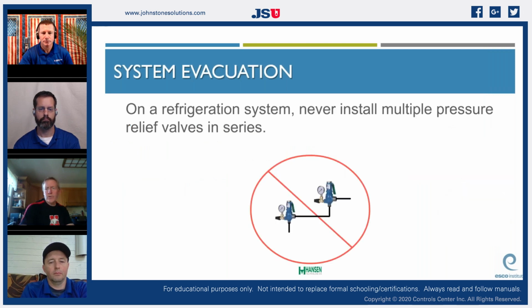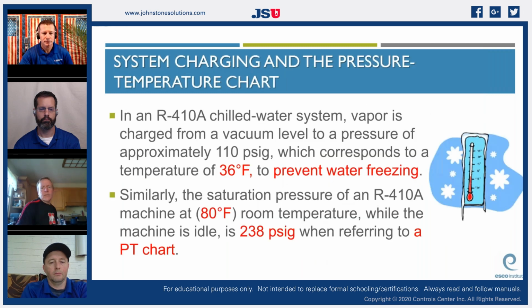Never install pressure valves in series, only in parallel. I don't work on a lot of chilled water systems, but they want to keep R410A at a PSI of 110 to keep the temperature at least at 36 degrees to keep the water tubes from freezing. So there's a little flex room there, but these pressure temperature chart relationships have been throughout this entire presentation, and these are important. As techs, we know that R22 is 57 PSI, I think, to stay above freezing, and R410A is right at 99 or 100, I think, to stay above freezing.